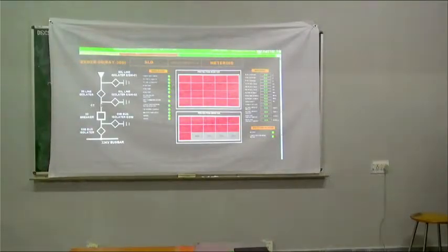Next, the trip circuit faulty. Trip circuit faulty means that when any fault occurs, that breaker should trip. That's why we should monitor whether the trip coil is healthy. A breaker has both a closing coil and a tripping coil. If any fault occurs and the trip coil is healthy, that breaker will trip the circuit. That's why we need to use the trip circuit faulty indication. If faulty, it will indicate positive; if healthy, it will indicate negative.